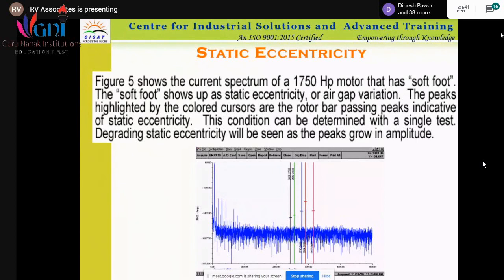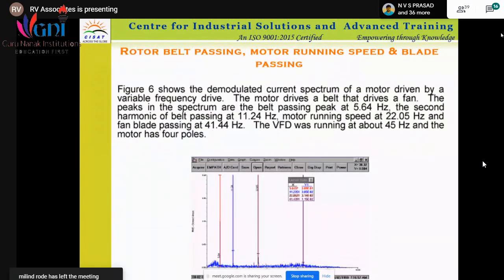Then there is a change in static eccentricity of the motor. It means unbalance. See the pattern. All these patterns have been gathered just because of the change in the current. There is only one input to the motor. The CTs are connected in all three phases. Whatever the current pattern is, that current pattern is studied by the software, and you will get the result.